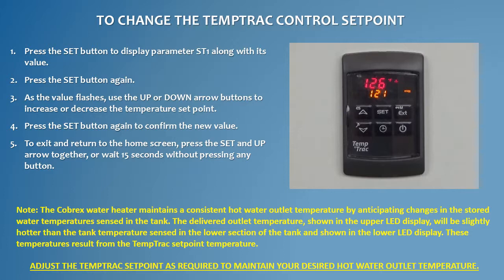Note, the Cobrex water heater maintains a consistent hot water outlet temperature by anticipating changes in the stored water temperatures sensed in the tank. The delivered outlet temperatures shown in the upper LED display will be slightly hotter than the tank temperature sensed in the lower section of the tank and shown in the lower LED display. These temperatures result from the TempTrack set point temperature. Adjust the TempTrack set point as required to maintain your desired hot water outlet temperature. Your Cobrex startup is now complete.